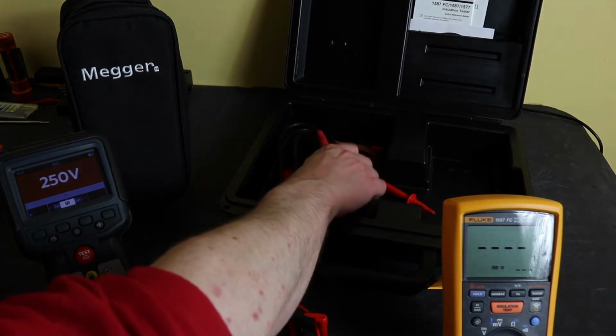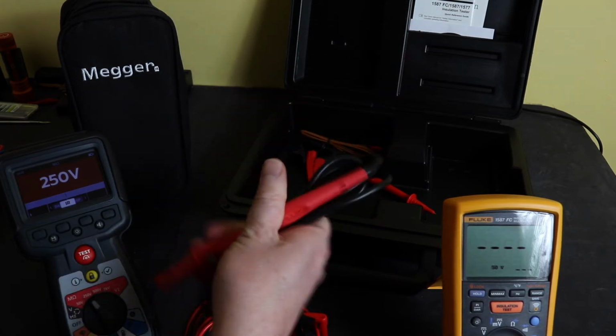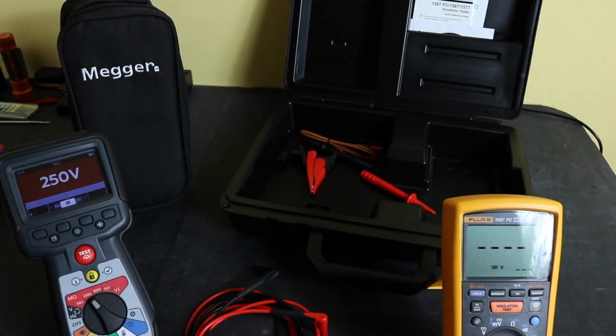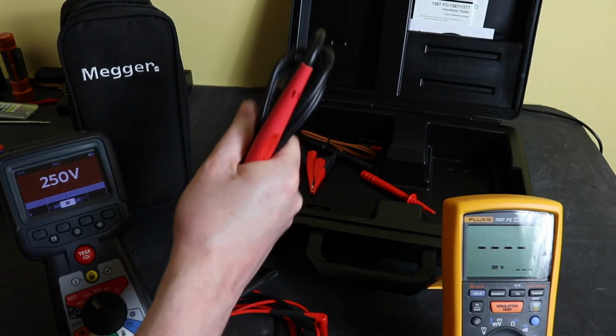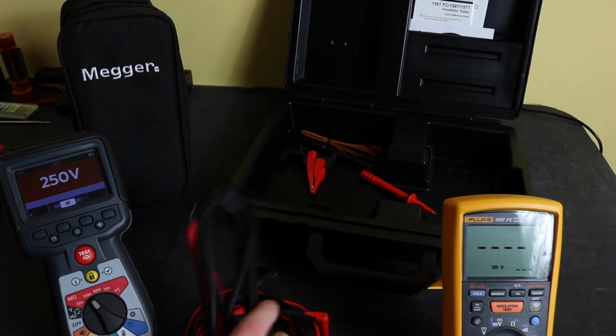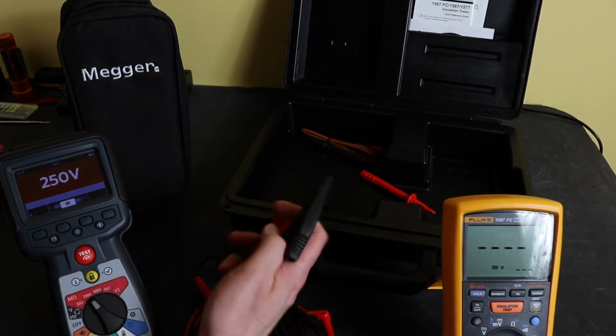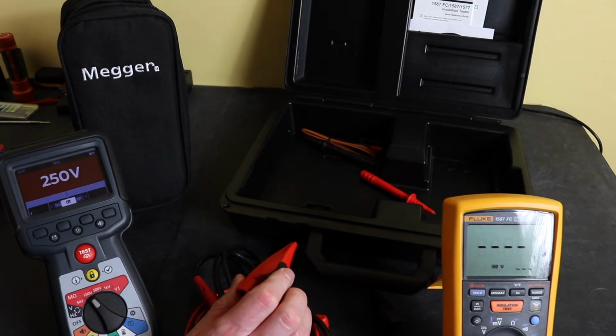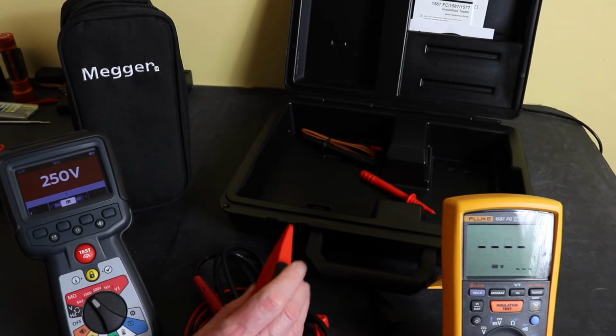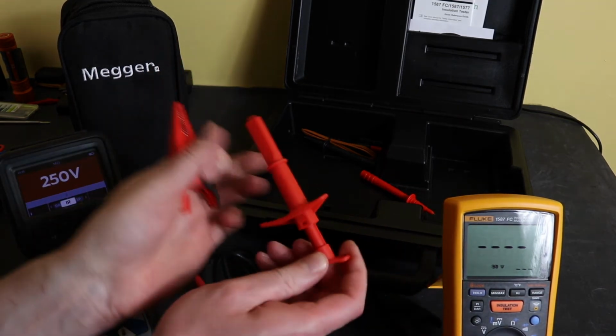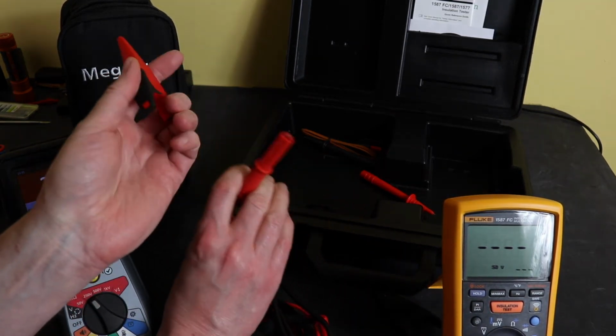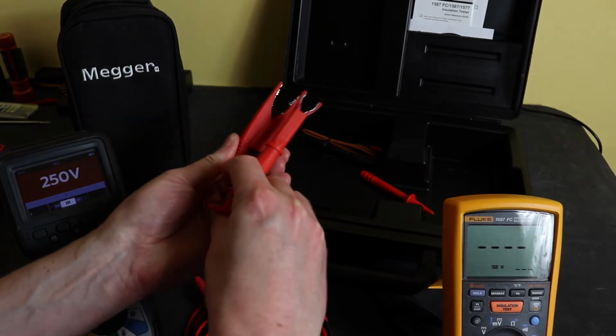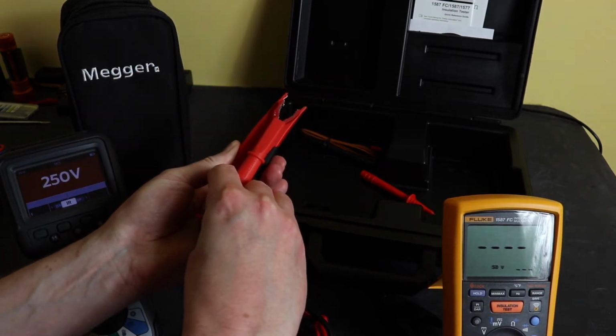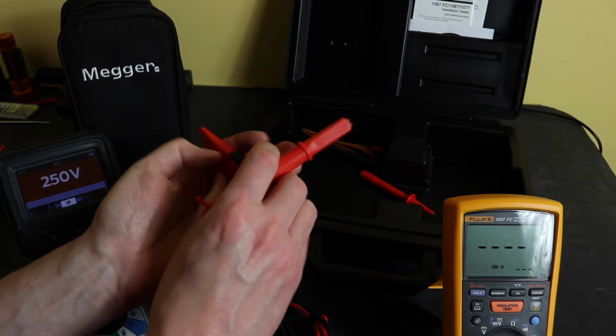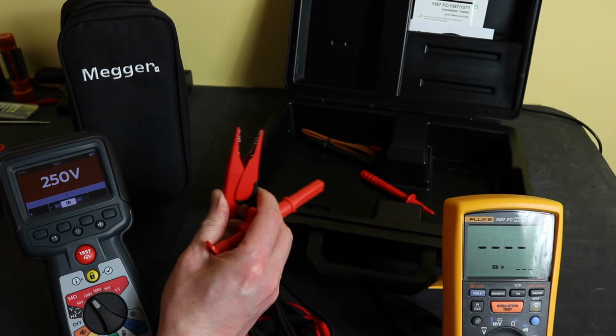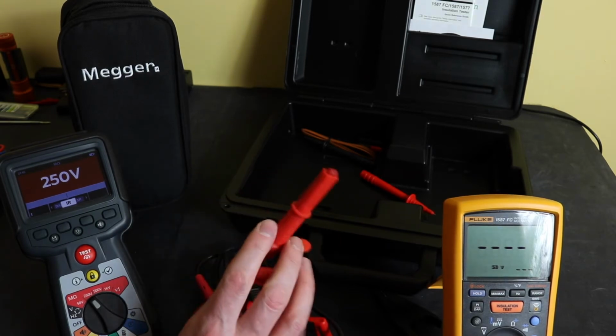You get the remote probe that is bespoke to the fitting on the instrument. You don't get this remote probe with the Megger. You get a set of croc clips, which in comparison to the Megger, you get these gripper style with this, which don't have the same opening as croc clips there, really. Quite a bit of difference between them. So for getting onto motor terminals, I do find these are much better than the offering from the Megger.